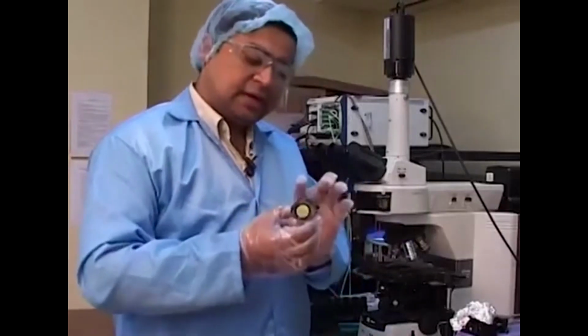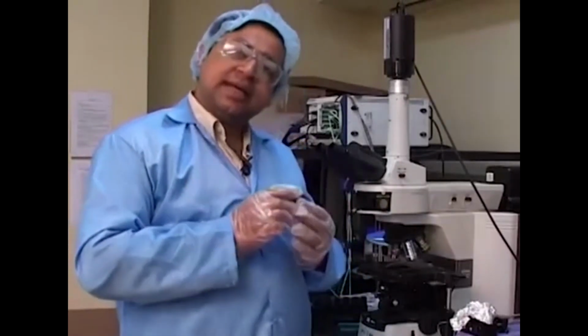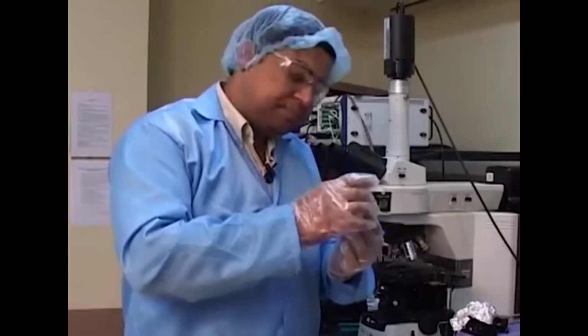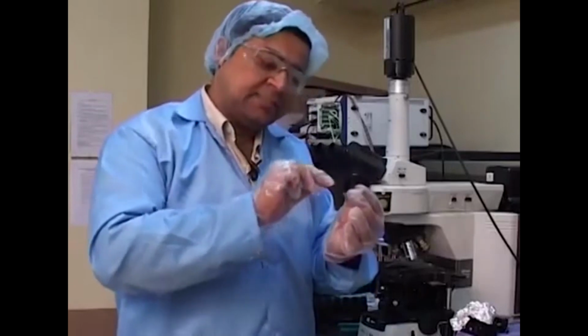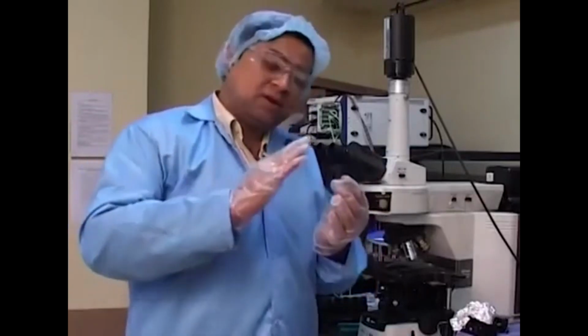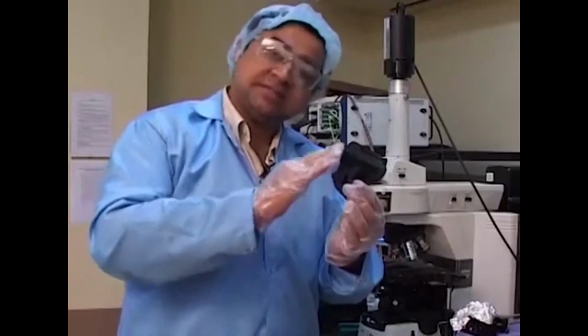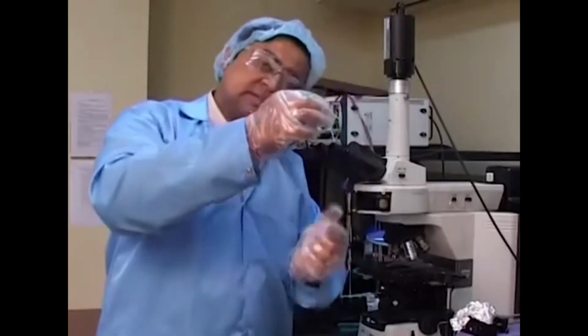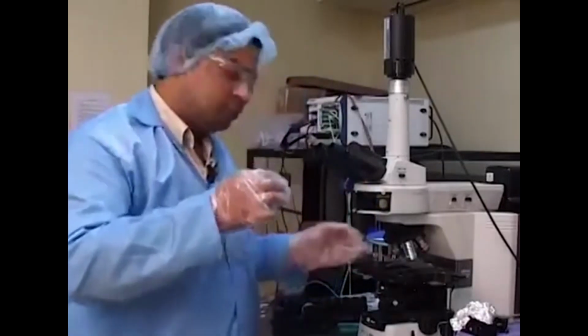So whatever cutoff we use should correspond to the excitation frequency of the fluorophore. Once this particular portion of light comes in the filter, it is reflected off the dichroic mirror, which is now placed at a 45 degrees angle, and actually goes down this filter cube to the objective.